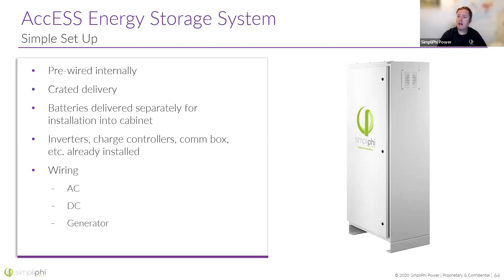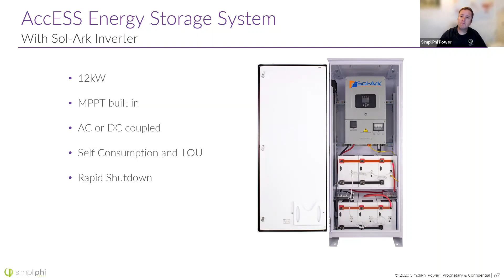Here's a picture with that Sol-Ark with those SimpliPhi batteries at the bottom. They're SimpliPhi again because we can see the COM ports. That Sol-Ark has built-in maximum power point trackers. We can program that to do self-consumption or time of use. It also has that rapid shutdown capability that a lot of people are looking for.